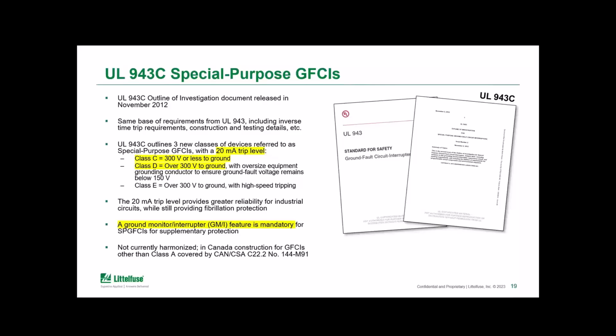So this document is really a game changer for industrial circuits because there is now a document that provides a path to standardized and listed devices for personnel protection that can be used on equipment at industrial voltage levels. So if there was a 480 volt circuit, this would be used with a Class C special purpose GFCI that would provide ground fault protection at 20 milliamps with integrated ground return path monitoring. So that's just to put those all together into one sentence.